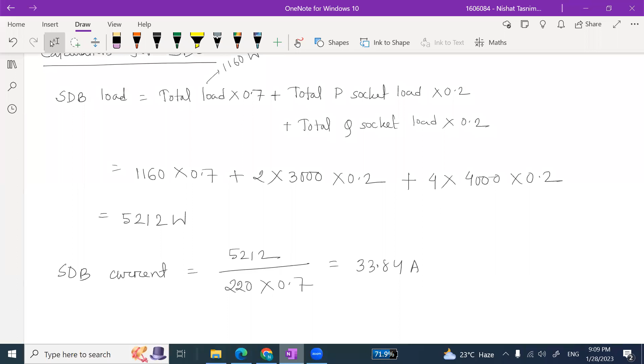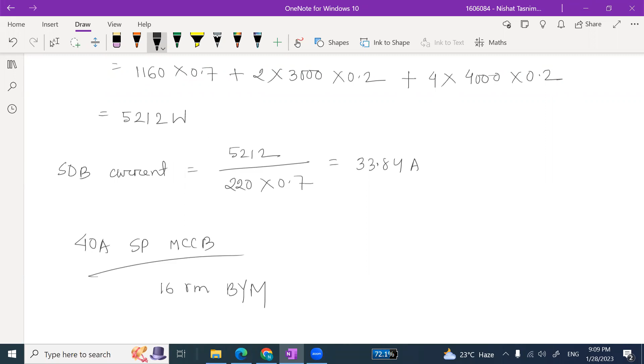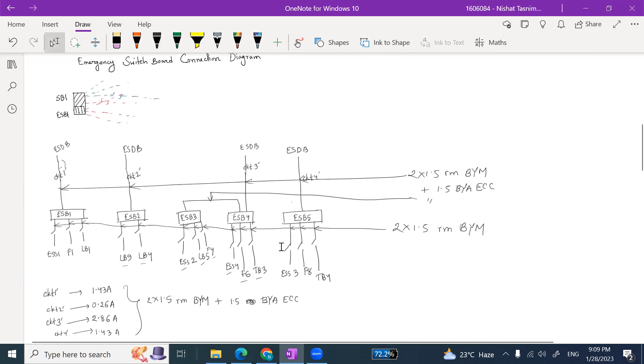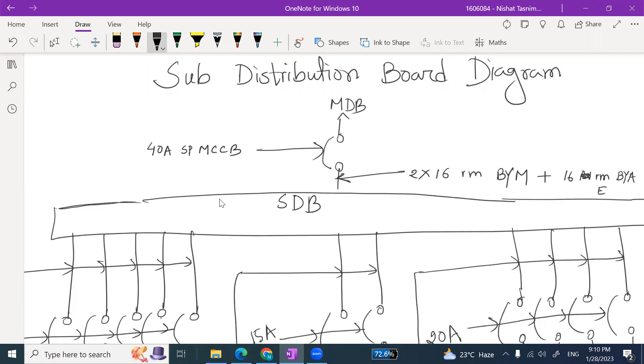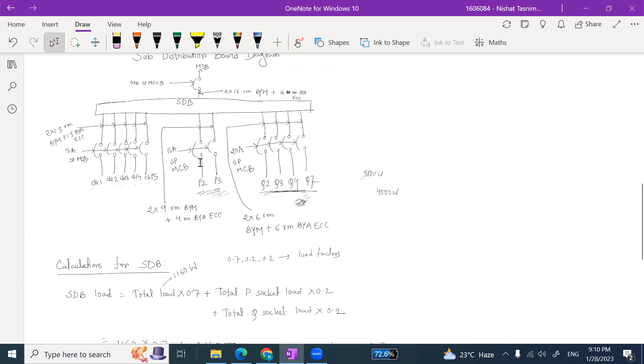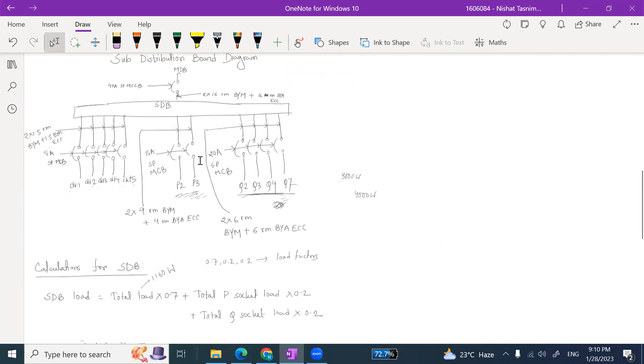And the conduit will be 16 Rm cable, 16 Rm wire. So we need to write it to the connection diagram. So now we will go to the connection diagram. Where is the connection diagram? Here. So here we will write 40 ampere single pole MCCB and 2 by 16 Rm BYM plus 16 Rm BYA ECC. So now our sub-distribution board diagram or SDB diagram is complete. Now we will go to the emergency sub-distribution board diagram.